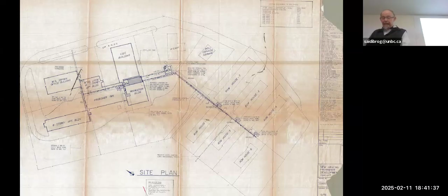This replaced a 56 million BTU per hour boiler in the power plant, which operating at high fire at 80% efficiency wasted 11 million BTU per hour up the chimney when it was operating on high fire. So, you know, that gives you cause to reflect on just how inefficient the original designers were. Energy wasn't an issue in the 60s. They never thought of the fact that you're wasting 11 million BTU per hour up the chimney. So that heating plant has now operated with minor modifications for 35 years and is still in use today.